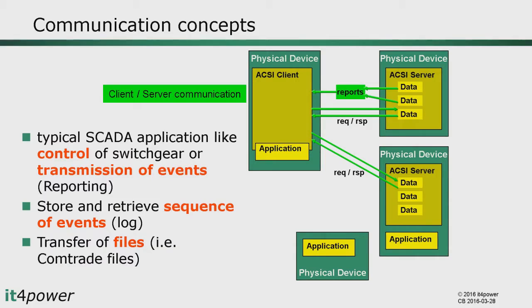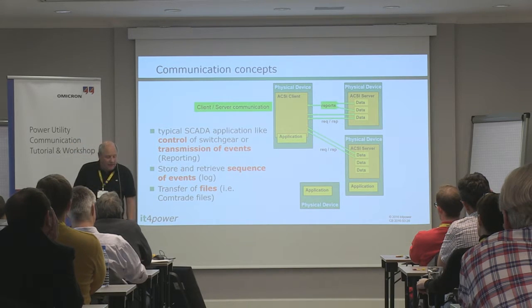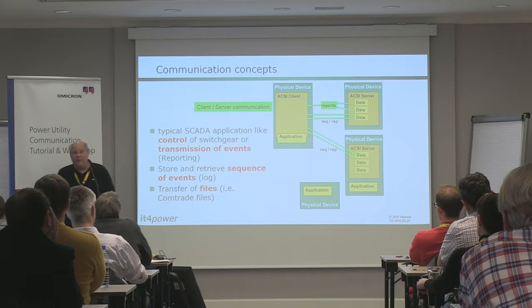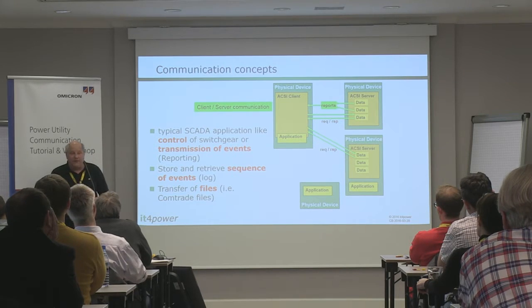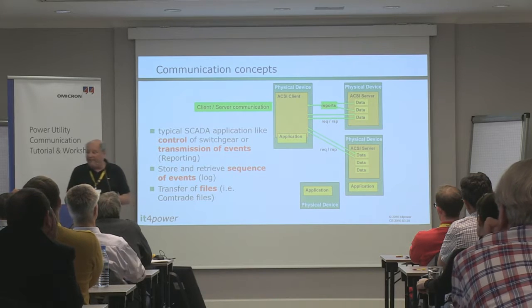The client-server model covers the major part of communication services defined in 61850. It is typically used for SCADA applications, control of switchgear, transmission of events, sequence of events, and file transfer. However, this is not necessarily suitable for time-critical applications, which are really one of the key differentiators of 61850.